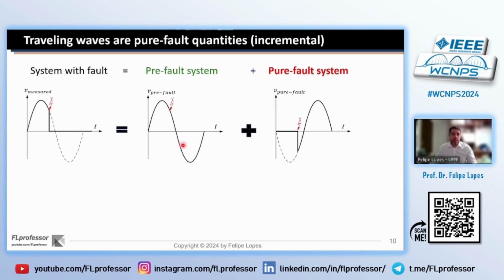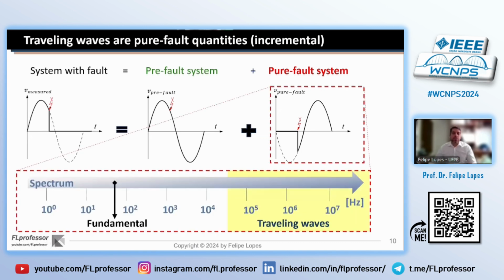The pre-fault system has information on the load flow through the system, but the pure fault system carries information on the fault only. And if we analyze the components present in the pure fault circuit system, what we can see is that there is, of course, a fundamental component. There are low voltage, low frequency transients that can show up here as well. But the higher frequencies are related to the traveling waves that will be launched by the fault and that will propagate over the line. And this is the part of the spectrum that we are interested in in this presentation.